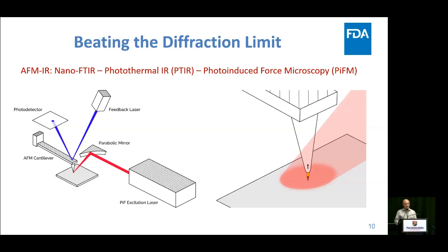There are two other techniques that are very interesting that are using quantum cascade lasers. It's a tunable laser at a specific IR absorption, so you can basically lock it into an absorption band of your material, and so you no longer really need the interferometer or the diffraction grating or anything. And in this case, you no longer even need an optical detector. What's really happening is you focus the IR beam onto your tip and onto your substrate. Two things can happen. One, if the IR beam hits an IR absorption band of the material, it can thermally expand. You can detect that thermal expansion using the AFM. Lateral resolution is high, but you need a thick sample, like hundreds of nanometers.